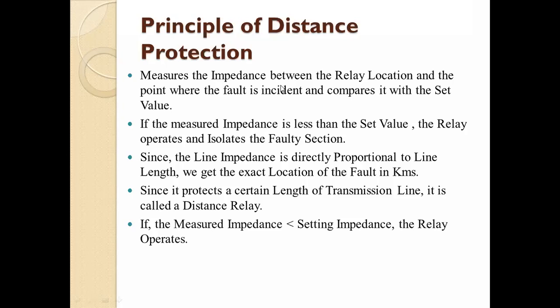What is a relay? If we consider the overcurrent relay, what we do is set one current value, called the pickup current. If the current flowing through that relay, or through that line or any equipment, becomes equal to or greater than that value, the relay will start operating. The same concept is used here for transmission lines - for distance protection we use impedance relays.